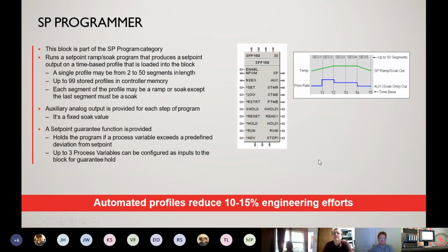Set point programmer block. This is another huge benefit in the HC900. If you drag and drop this block onto the programming page, that allows you to have a set point programmer which can ramp and soak temperatures or process variables over a specific time. So you can store up to 99 profiles into the set point programmer block, where you then can name them and go back and choose a specific set point programmer that you want to run. These are typically used in batch applications. We use it a lot in the heat treat world, but you can use it on other applications as well.